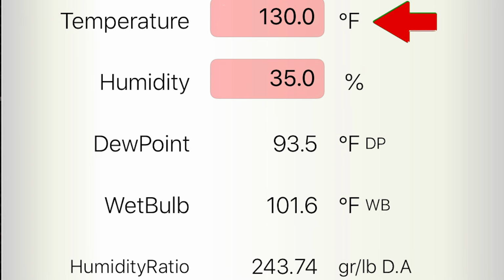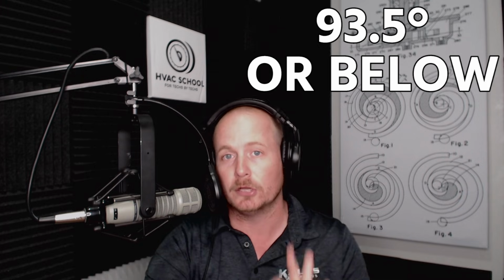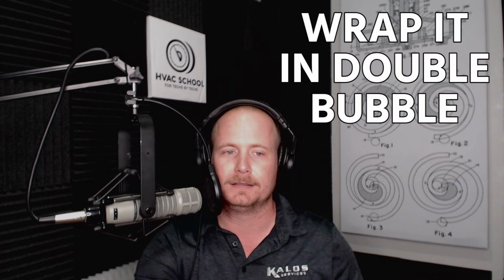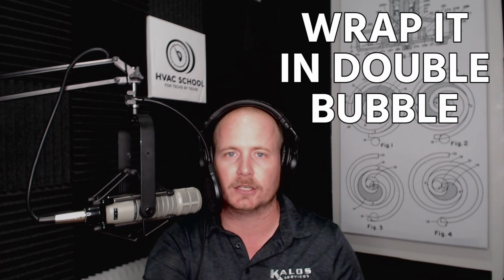If you plug in 130 degree attic temperature, which is something we see in Florida quite often, even if you have a 35% relative humidity in that attic, that is a dew point of 93.5 degrees Fahrenheit, which means that any surfaces in that attic that get to 93.5 or below are going to start condensating. And that's very easy for supply ductwork to achieve that. Now, there's a couple different techniques you can use to solve this issue. You can use higher R value supply ductwork, or maybe wrap it in something like double bubble, some sort of another insulation on top of that.